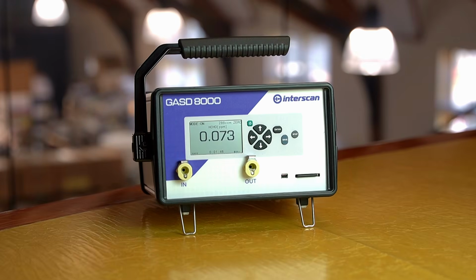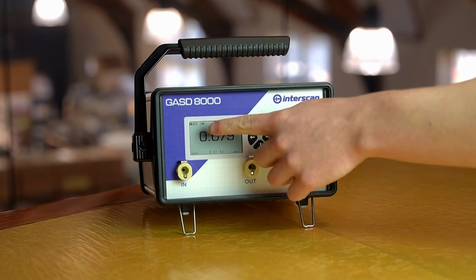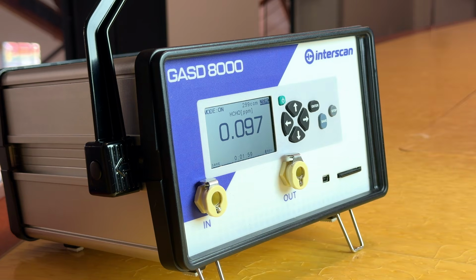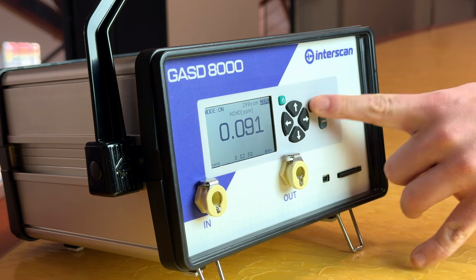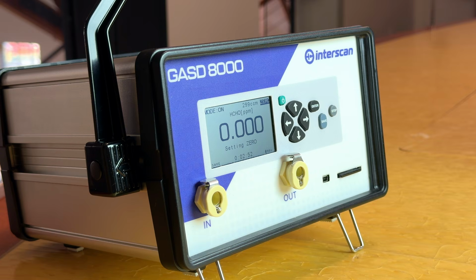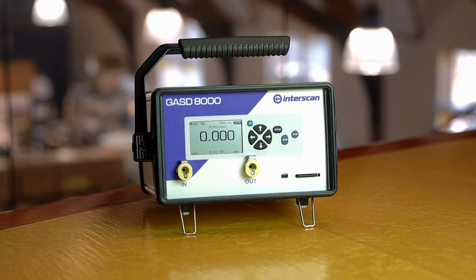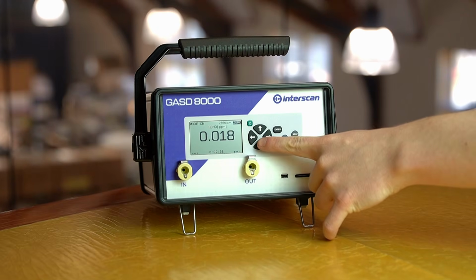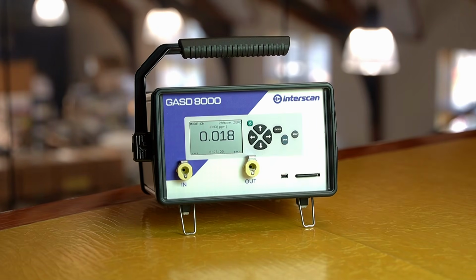Before sampling, the analyzer must be zeroed in clean ambient air. While in on mode, press the up arrow to activate zero mode. Press Enter to set zero. The reading will gradually move towards zero as the instrument calibrates. You should see positive, non-zero values fluctuating and not just all zeros continuously. Otherwise, your zero will be set too low, and when sampling, you may get lower than true values. When complete, press the down arrow to exit zero mode.